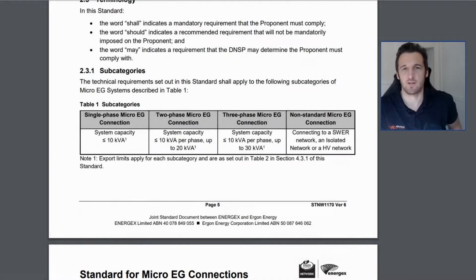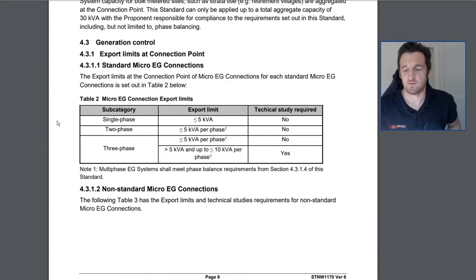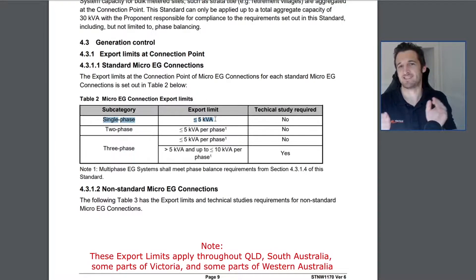Before I go into defining what export limiting is, I'm just going to refer to the Energex metering manual to show what households are allowed to install in the way of solar. Referring to table one here of single phase micro EG connections, you'll see we can have system capacities up to 10 kVA or up to 10 kilowatt inverter capacities on single phase. However there is a note saying export limits apply for these installations — single phase export limited to 5 kW. So you can install 10 kW on single phase but it's export limited to 5 kW. That's the main takeaway.